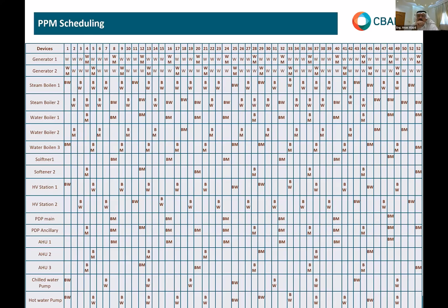So you divide the 52 weeks, which is the weeks of the year for 2021, for example, and then from the manufacturer manual of the equipment, or from best practices, we also accept that, you start putting all of these on the schedule. Plus, if you have multiple equipment, you make sure you spread them in different weeks. You don't want to lose all the equipment in the same week. So if I have 3 sterilizers and these sterilizers need quarterly maintenance, I put them in different weeks. So every 3 months we do.